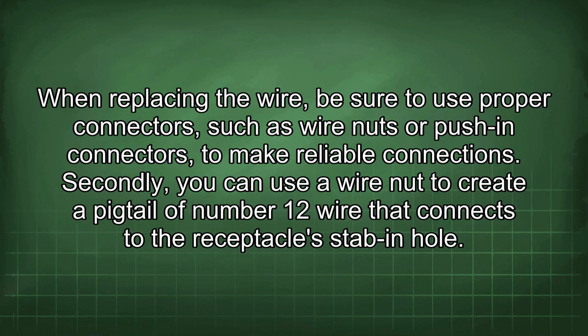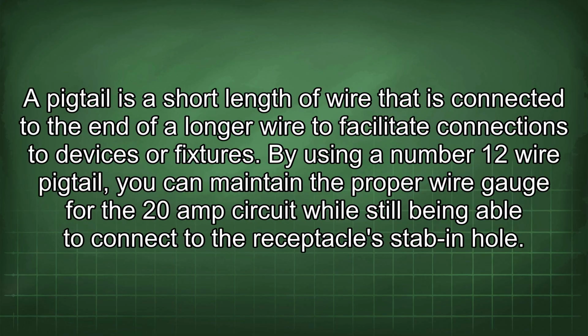Secondly, you can use a wire nut to create a pigtail of number 12 wire that connects to the receptacle stab-in hole. A pigtail is a short length of wire that is connected to the end of a longer wire to facilitate connections to devices or fixtures. By using a number 12 wire pigtail, you can maintain the proper wire gauge for the 20 amp circuit while still being able to connect to the receptacle stab-in hole.